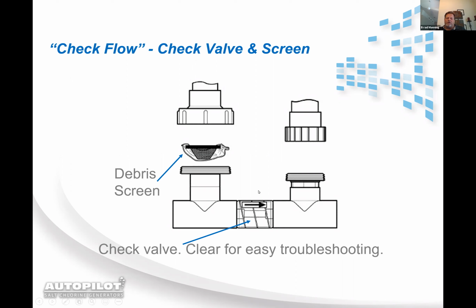Also, I will tell you, on commercial applications, a lot of check flows I get, we looked at that picture earlier that had the big butterfly valve in between the two manifolds that were split off. A lot of times, the pool guy will come in there looking to get his flow rates up, and he'll open up that butterfly valve, and that'll rob water from our manifolds, and you'll wind up with a check flow message.